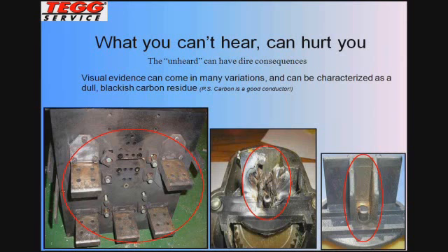And I get a lot of questions about decibel level. And although decibel level is a very important parameter, when it comes to electrical, it cannot be used as a gauge for severity. For my purposes with arcing, tracking, and corona, the dB level increasing only represents how close I am to the source of that emission. It has nothing to do with severity in most cases. So the higher the dB level, the closer I am to the source. We use that as a technique to isolate down where the origin of the emission is coming from.